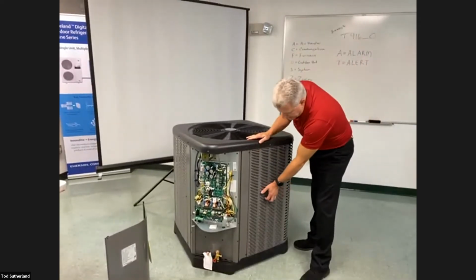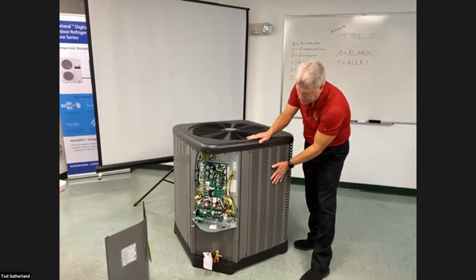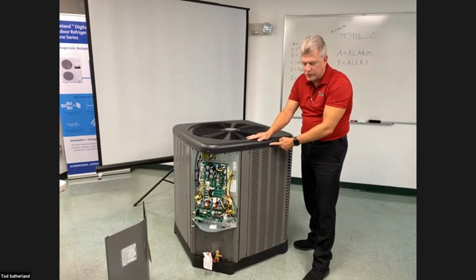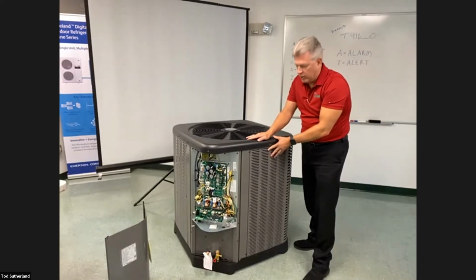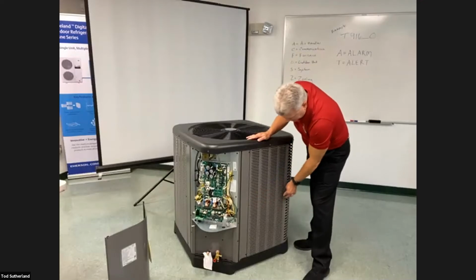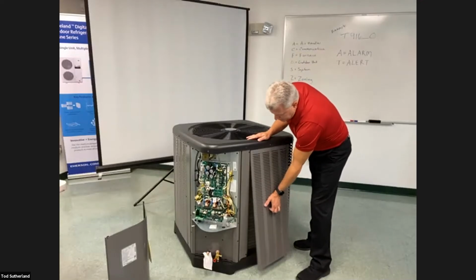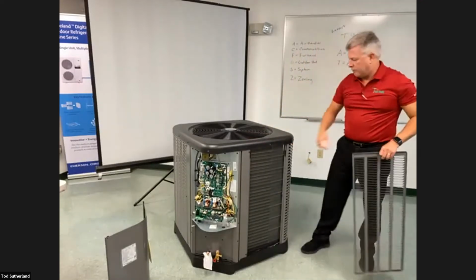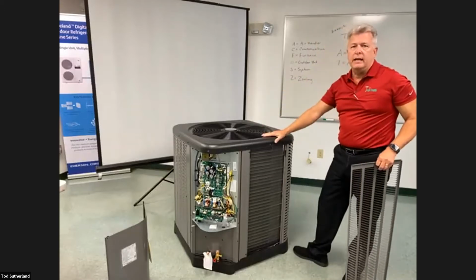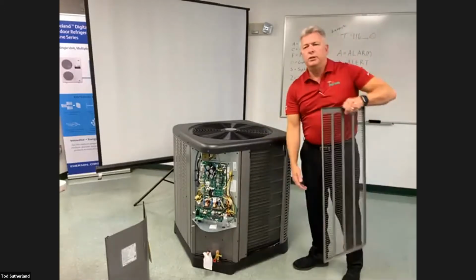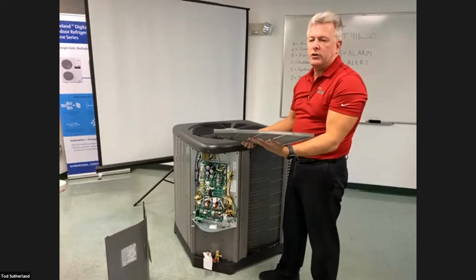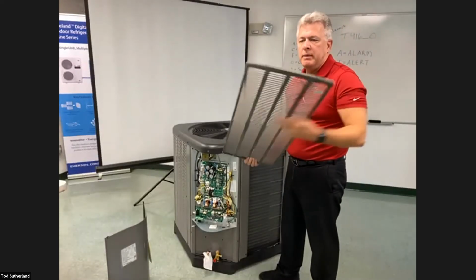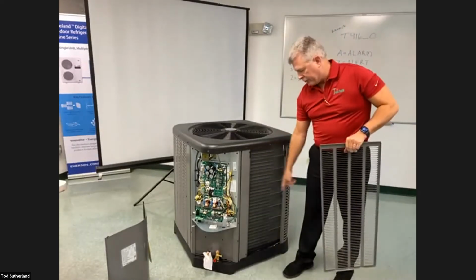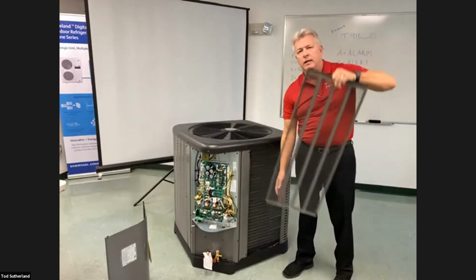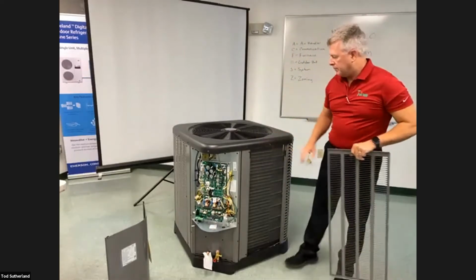You also have these single panels here. I've already removed the screws. On the smaller units, you just have 1 screw here to remove these panels. On some of the larger units, you're going to have a screw here, a screw here, and a screw here. But once you've removed those screws, the panels pull up and you can remove those all the way around for easier cleaning of the unit. Okay. You also will notice that these panels are slightly warped, and they're meant to be that way so that when they're put in here, there's grooves that they lock into. Then you have to twist it to lock it back up into the unit, which helps prevent any vibration that goes on in the unit.